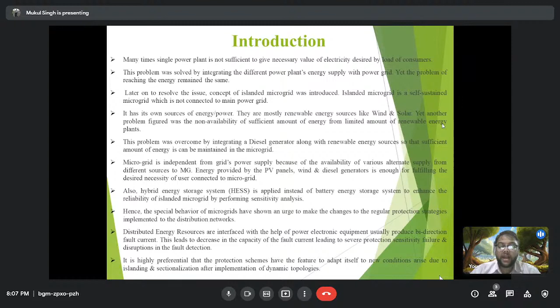This leads to severe protection sensitivity failure and disruption in fault detection. It is highly preferable that the protection scheme have the feature to adapt itself to new conditions arising due to islanding and sectionalization after implementation of dynamic topologies.